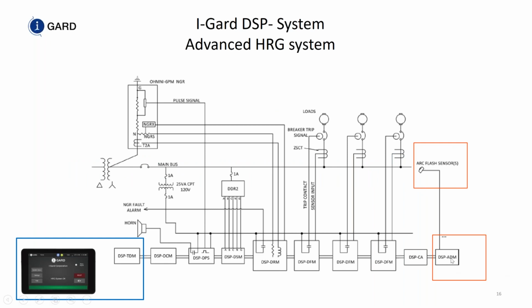So we developed a DSP arc detection module, which is part of our system over here. What we do is we detect an arc flash through the detection of light. When we see the light, we quickly isolate the system and take it offline. Therefore, the only way you can reduce incident energy in any type of system is to remove the fault as quickly as possible. So we can detect that fault in less than 1 millisecond and then clear the fault within 100 milliseconds. So we're not relying on conventional overcurrent relays to clear the fault. We actually use light to clear the fault, and it's integral to iGard's HRG advanced system.